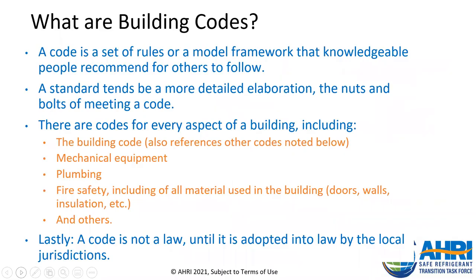So moving on, another aspect of ensuring safety and performance of equipment in buildings is building codes. Building codes are also a means of enforcing safety standards or lawfully requiring them in the US. A building code, as it says here, is a set of rules that specifies the standards for constructed objects, such as building and non-building structures. The main purpose of a building code is to protect public health and safety. While product safety standards are implemented by manufacturers, building codes are applied by architects, building constructors, inspectors, interior designers, engineers, etc., and enforced by code officials or inspectors.